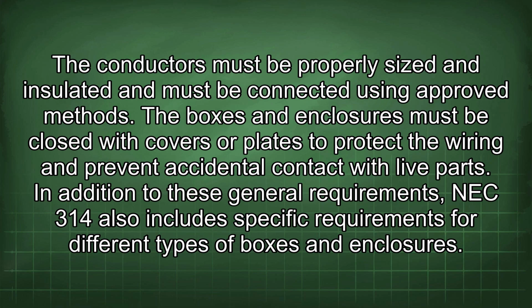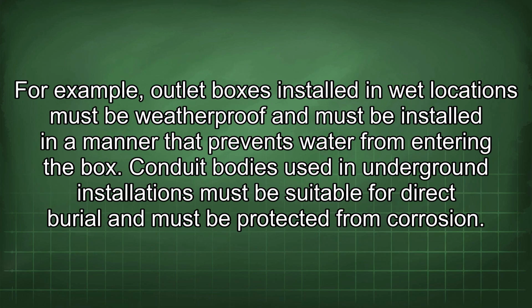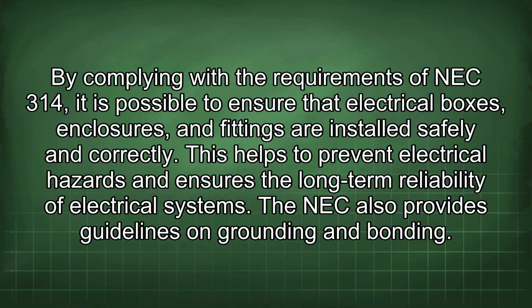In addition to these general requirements, NEC 314 also includes specific requirements for different types of boxes and enclosures. For example, outlet boxes installed in wet locations must be weatherproof and must be installed in a manner that prevents water from entering the box. Conduit bodies used in underground installations must be suitable for direct burial and must be protected from corrosion. By complying with the requirements of NEC 314, it is possible to ensure that electrical boxes, enclosures, and fittings are installed safely and correctly. This helps to prevent electrical hazards and ensures the long-term reliability of electrical systems.